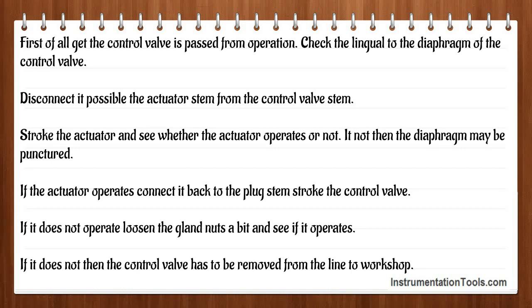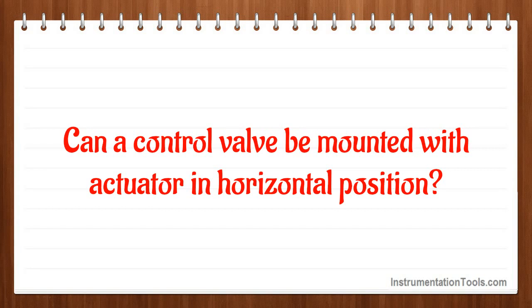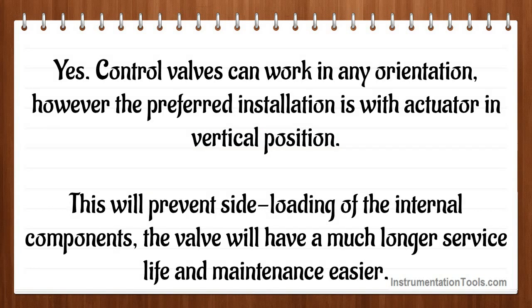Can a control valve be mounted with the actuator in horizontal position? Yes. Control valves can work in any orientation; however, the preferred installation is with the actuator in vertical position. This will prevent side loading of the internal components. The valve will have a much longer service life and maintenance will be easier.